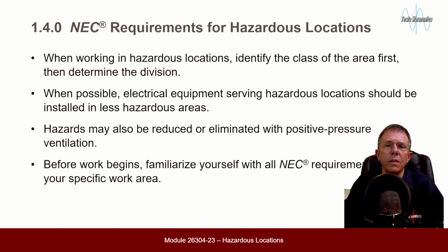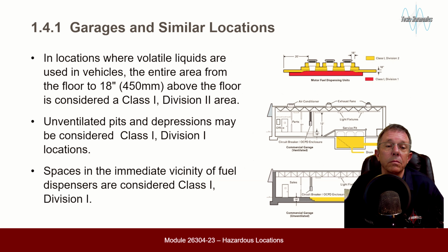NEC requirements for hazardous locations. When working in hazardous locations, identify the class of the area first and then determine the division. When possible, electrical equipment serving hazardous locations should be installed in less hazardous areas. Hazards may also be reduced or eliminated with positive pressure ventilation. Before work begins, familiarize yourself with all the NEC requirements for your specific work area.